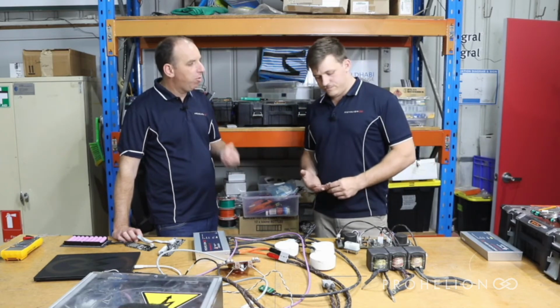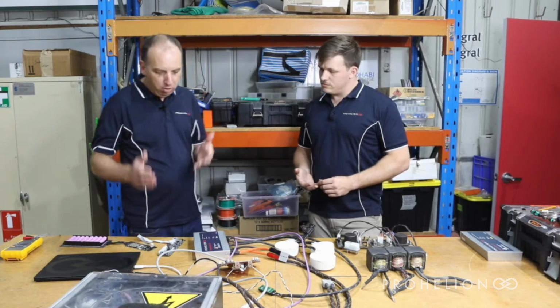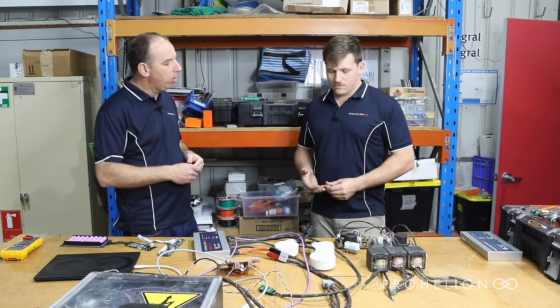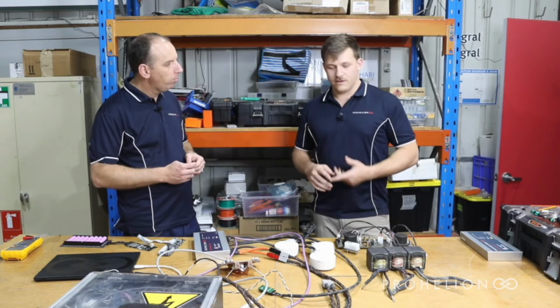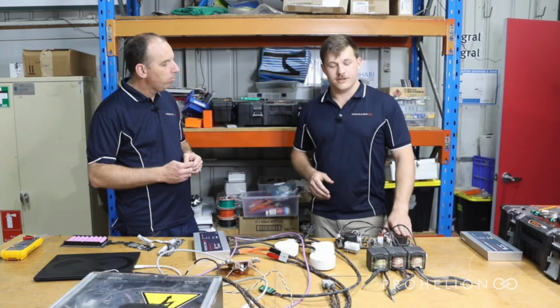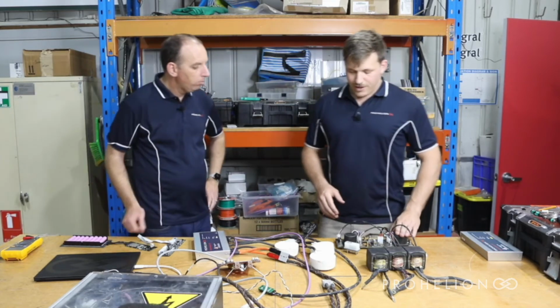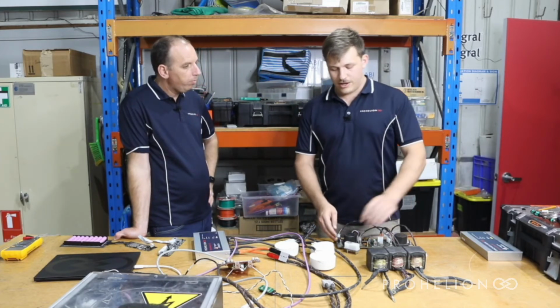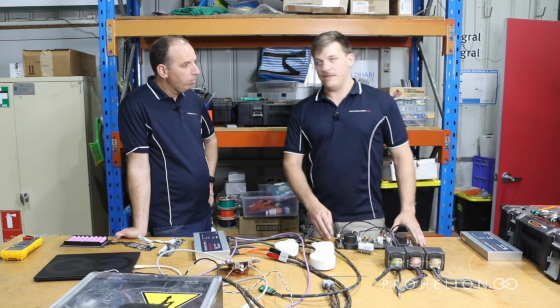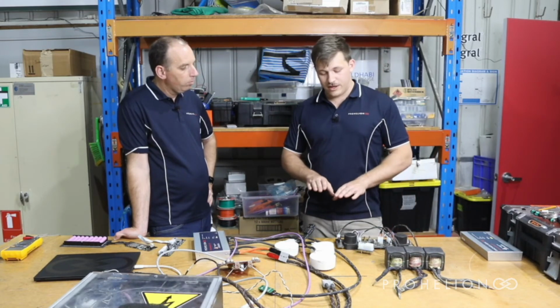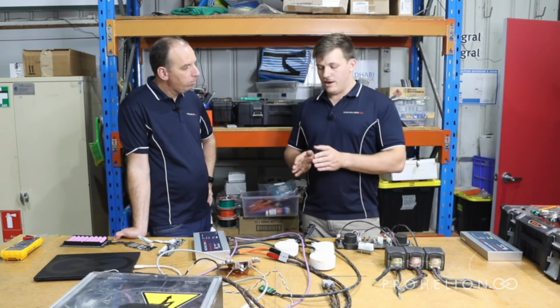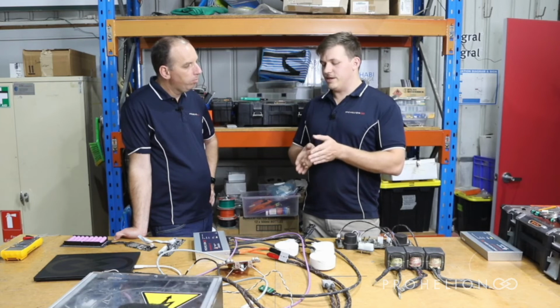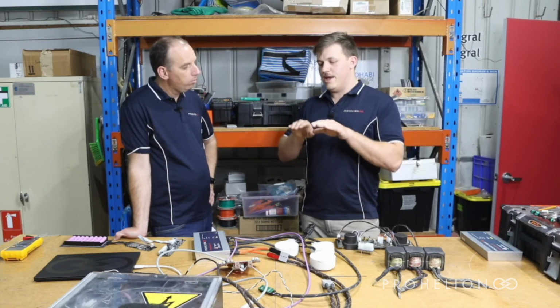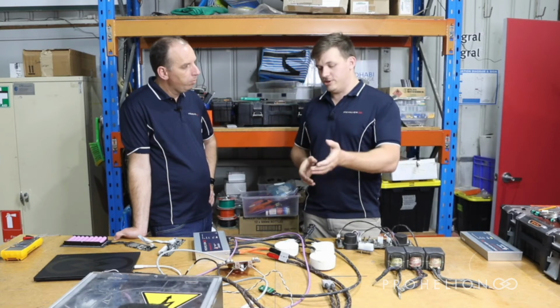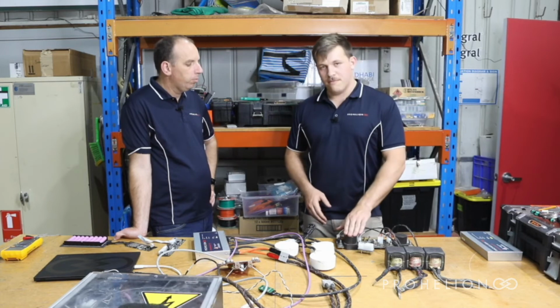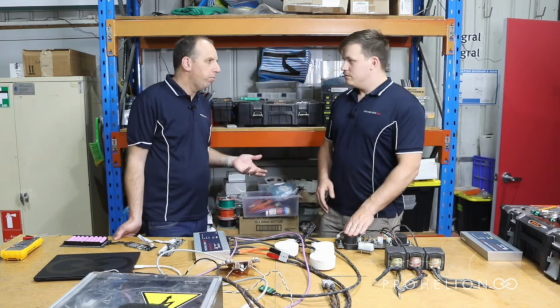And so what are the steps that are going on in that precharge process? When you say to the BMU engage, what's actually going to happen then? What's the BMU going to do? So the first thing that the BMU is going to do is engage the negative contactor, and then the next stage is to engage the precharge contactor. At that point, it starts measuring the voltage of the output while simultaneously measuring the battery voltage. And then once that output voltage rises to the same level as the battery voltage, or within a set threshold that you can configure within the BMU, it will engage the main positive contactor, at which point the current flows normally.